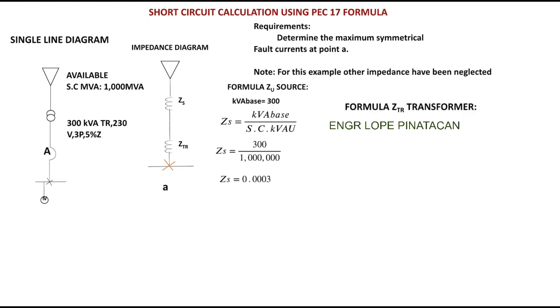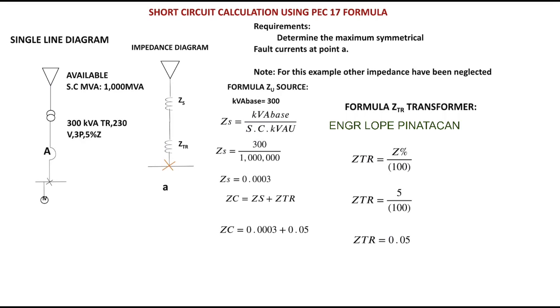So next we need to know the impedance of the transformer. So this is the formula of the impedance of the transformer: the percent impedance divided by 100. So we have 5 divided by 100, so we have 0.05 impedance. So now we have the value of the source impedance and the transformer impedance. So in our impedance diagram that is in series, so we will add the results of these impedances. So the combined impedance equals the source impedance plus the transformer impedance.